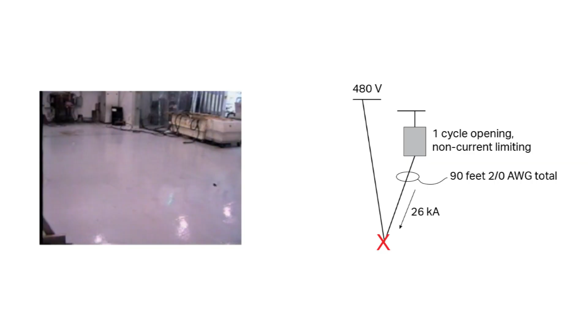This test visually shows the destructive forces associated with fault current. Extreme magnetic or mechanical forces can be seen during this test. However, a 200 amp non-current limiting protected device used to protect this 2-aught conductor would be properly sized per the National Electrical Code. Proper bracing, support, and torque are needed to keep this conductor from pulling out from its terminations and causing additional safety hazards.